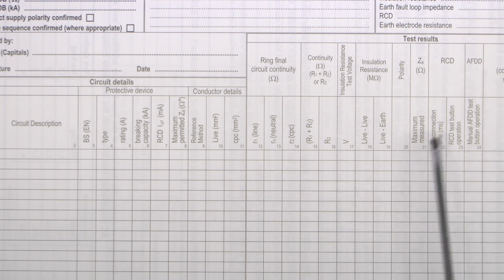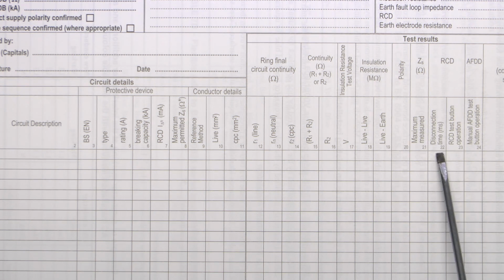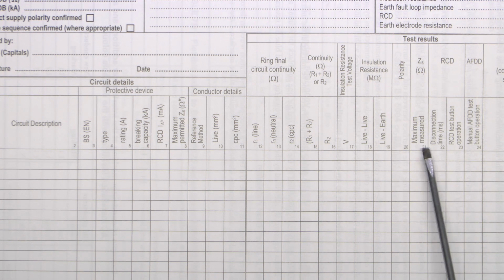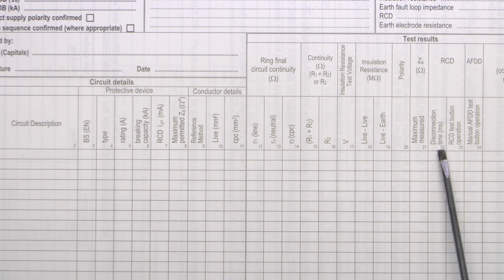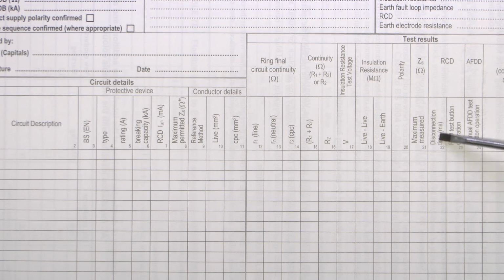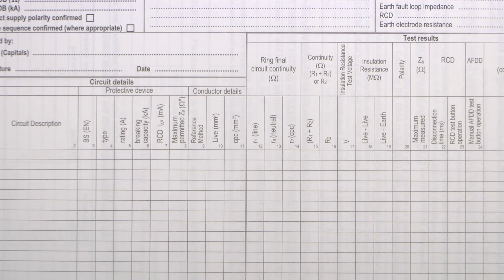Now what's been removed here for the RCD: we've still got the disconnection time here, but you'll notice there's only one column. Previously there were two columns for the 1x and 5x, so now it's just been mangled together into the disconnection time. And presumably the intent here would be to just have the shortest one, which is going to be the one at 5 times, and we've seen that in the previous parts of this as well.